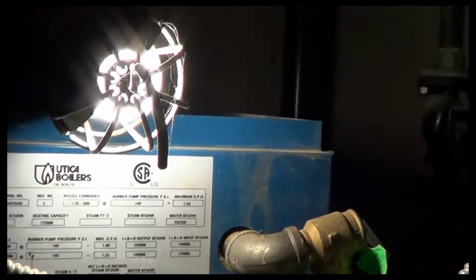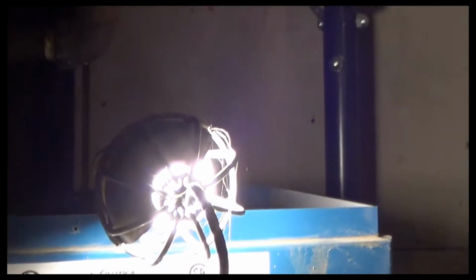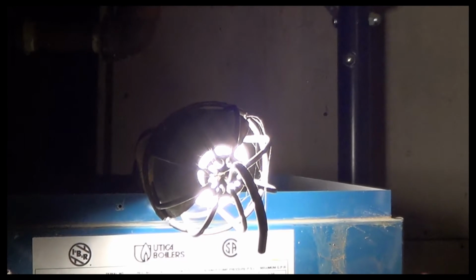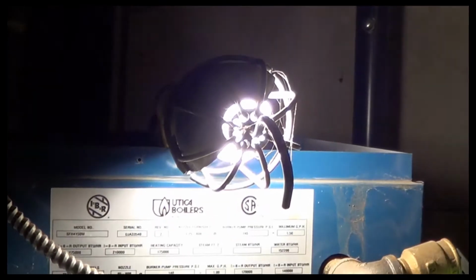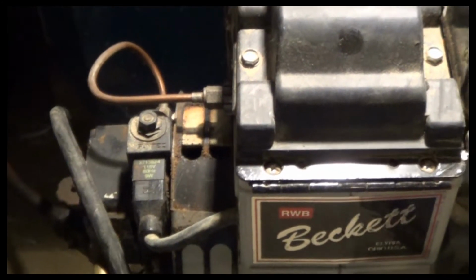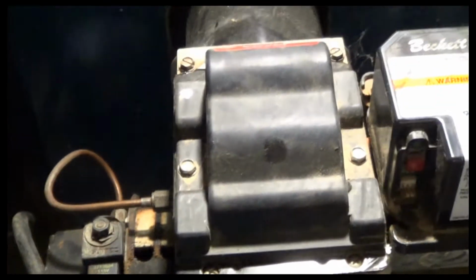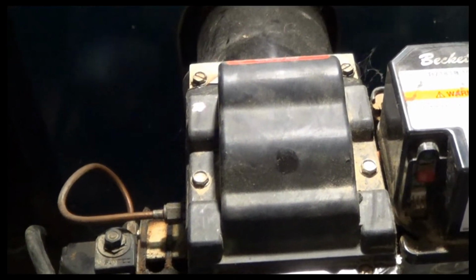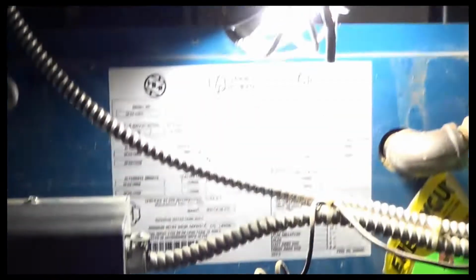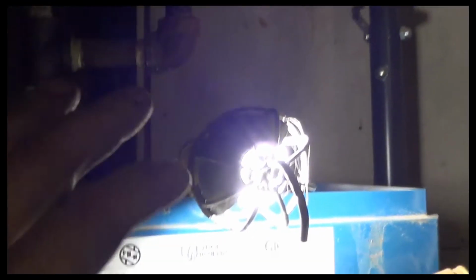I'm going to get this done, get that done. I'm going to combust. First, I'm going to get it to a zero smoke, folks. Don't put your combustion analyzer in there until you're at a zero smoke. If you put it in there and you're at a zero smoke already, come down here, turn that air down, until you get just a trace of smoke, okay? And then you work your way back to a zero smoke, because if you don't do that and you got a zero smoke right off the bat, you're probably running too much air.